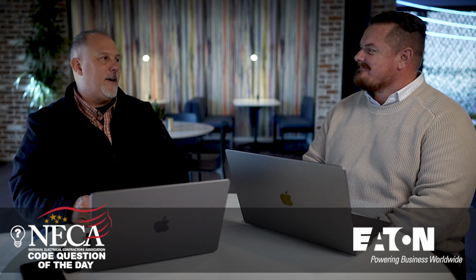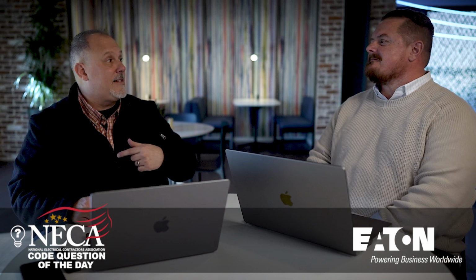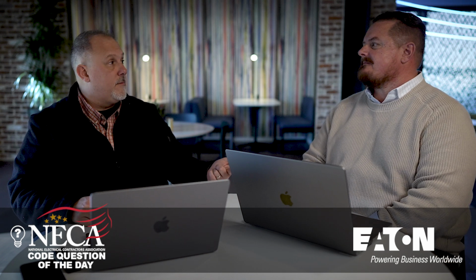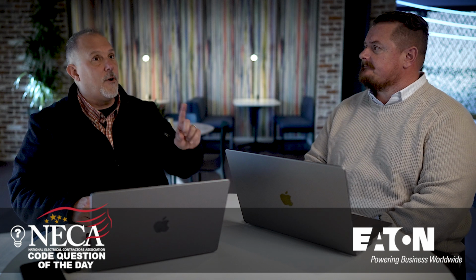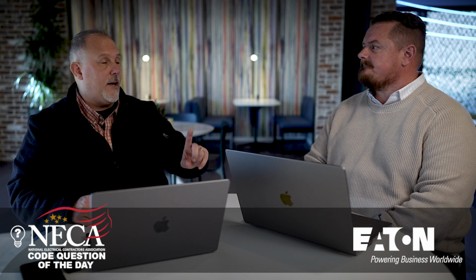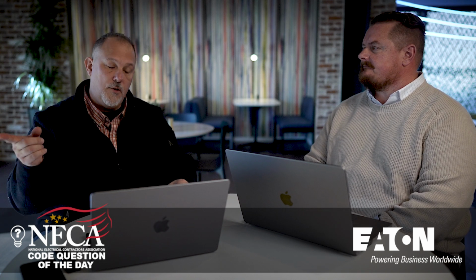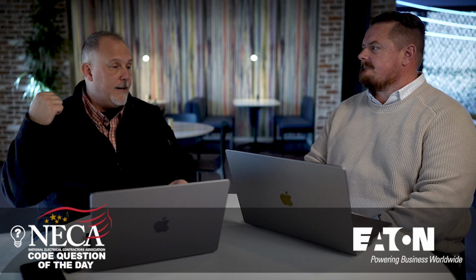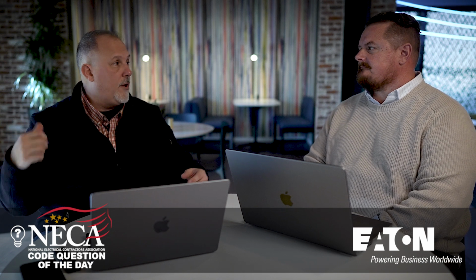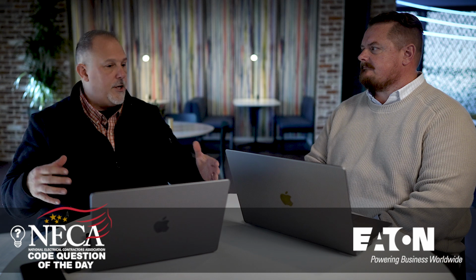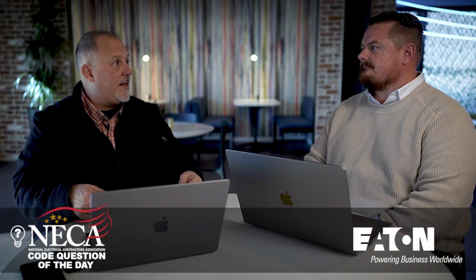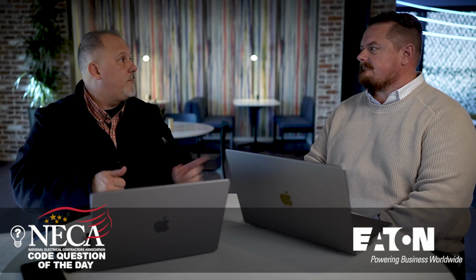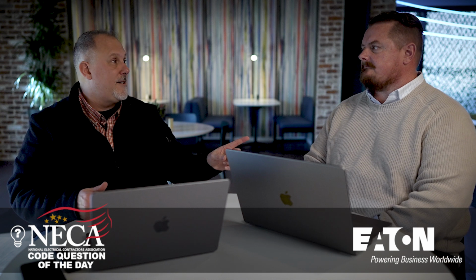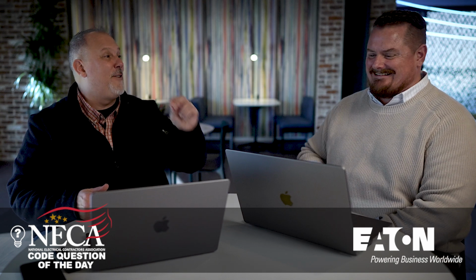That's absolutely right. The other one that I see a lot of are elevator control panels. Yeah. And where I see it the most, I would get calls from Seattle, Washington, New York City, Pittsburgh, Houston, those big cities with secondary networks. You got like 200,000 amps at the base of the building, and then you run busway. I call busway high efficient fault delivering system.